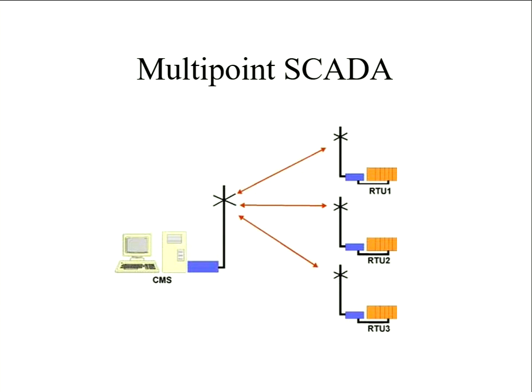But ultimately the ultimate safety usually sits on something that's pneumatic, so it doesn't even rely on the power, so you've got levels of redundancy and safety. So a control room will be scanning multiple ones of these, and it'll go, give me your analogs, give me your analogs, give me your analogs, and we were scanning typically at 1 minute frequency. Usually you have a capability of looking faster, so if somebody's doing some maintenance work on the site and you don't want to wait till the scheduled update, you can either press a button and say give it me now, or say put it on fast scan, tell me every second for the next 3 minutes.